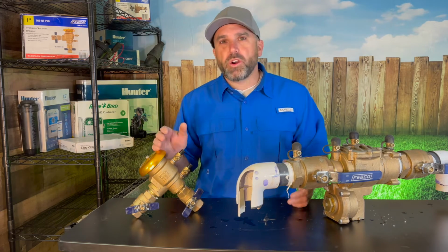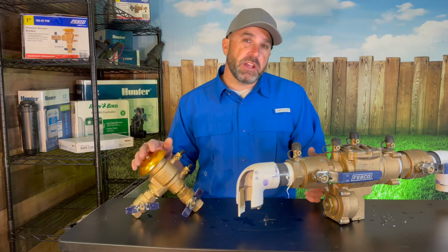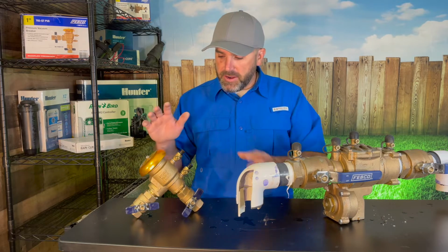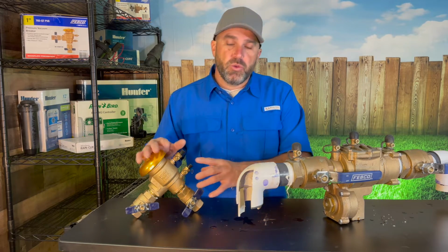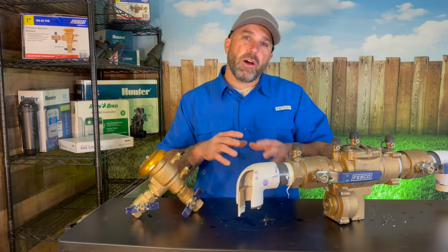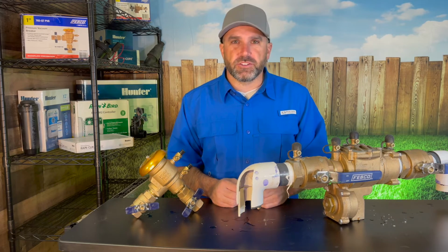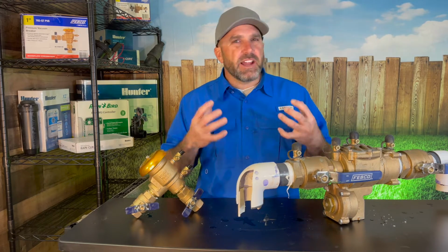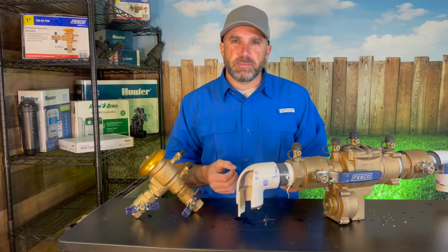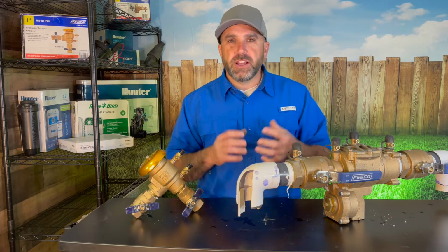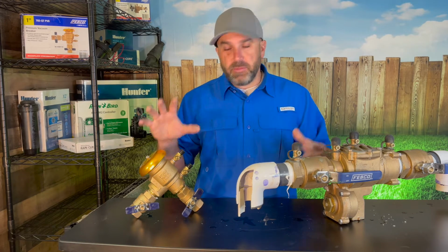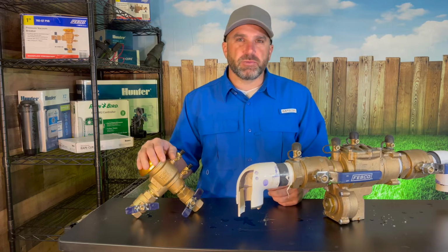If you want all the water out, you can call a guy that has a big air compressor, and he'll come out and tie on to where the backflow device is, and he'll blow out all of the water out of your sprinkler system. That way, when it gets down to those really cold freezing temperatures, that water's not going to freeze, and it's not going to freeze your backflow device or the piping of your sprinkler system.